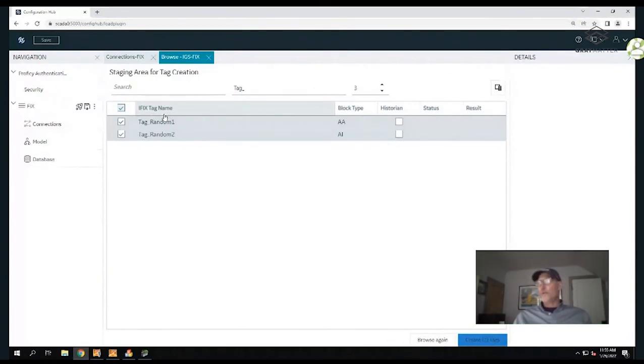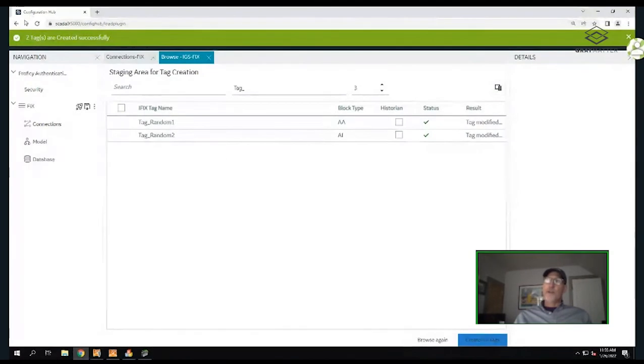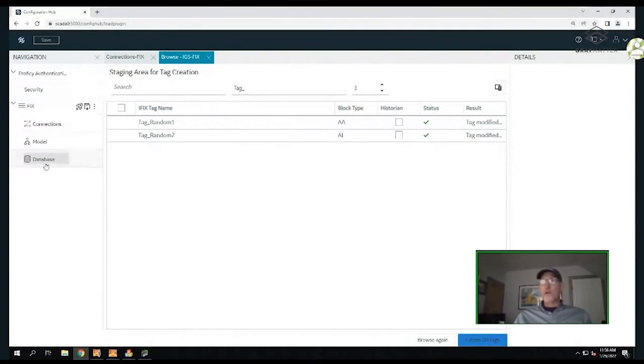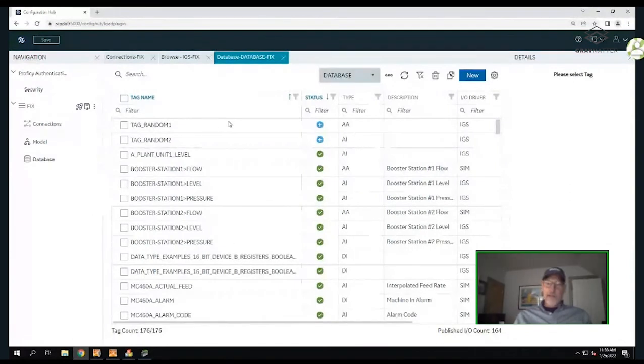I can do this online without using the database manager we used in the past. Once satisfied with the configuration, down at the bottom right is a Create Tags selection. I'll do that, and you'll see up top it says two tags were created successfully. Going to the Database navigation, you'll see it brings up another tab showing the two tags I just created. I didn't have to type in an IO address or look at my IGS driver - just click and drag.